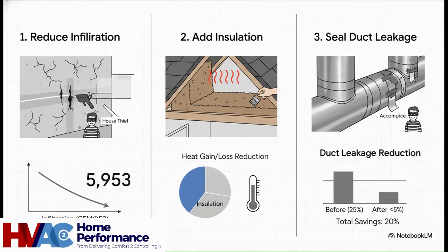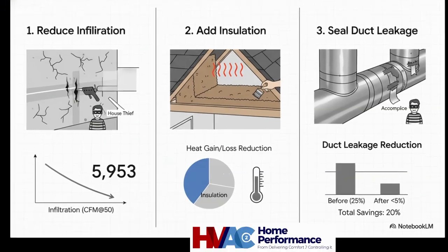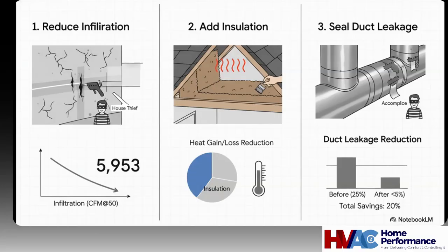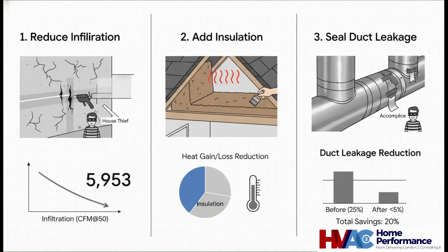It was a three-pronged attack. First, go after the primary thief: air seal the house with a goal of cutting that massive infiltration from over 9,400 down to a target of 5,953 CFM. Second, beef up the home's armor by adding R38 insulation to the attic. And third, hunt down and eliminate that accomplice by meticulously sealing all that ductwork.